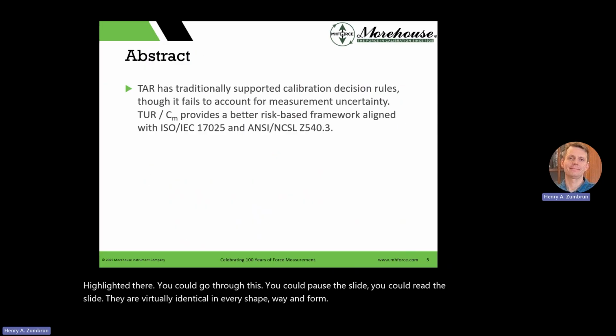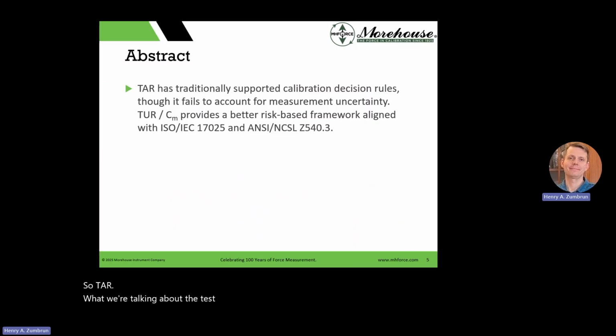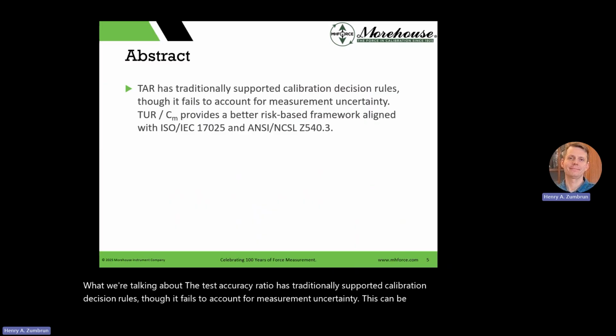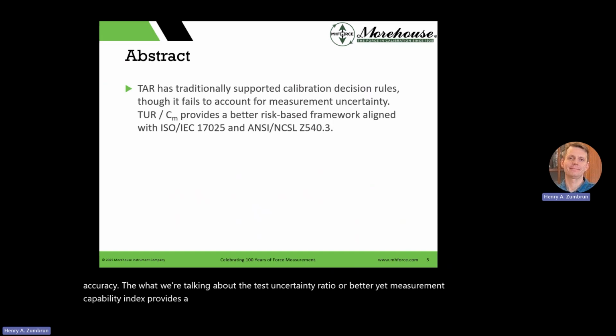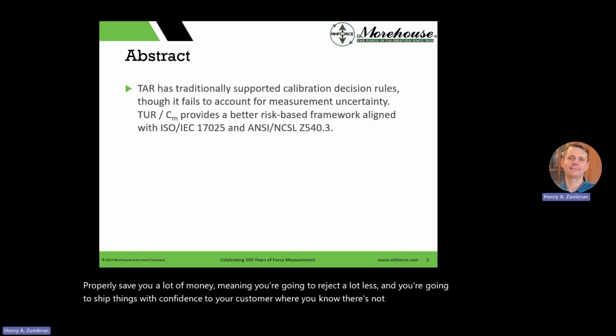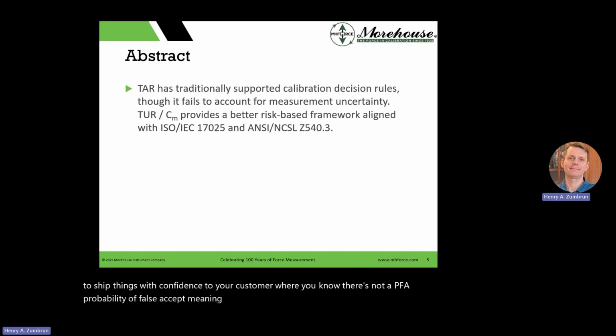So TAR, the test accuracy ratio, has traditionally supported calibration decision rules, though it fails to account for measurement uncertainty. This can be very problematic depending on how that manufacturer designed and quantified their accuracy. The test uncertainty ratio, or better yet, measurement capability index, provides a better risk-based framework. And if you're doing things properly, that is going to save you a lot of money, meaning you're going to reject a lot less and you're going to ship things to your customer with confidence, where you're pretty sure, better than 98% sure, that what you're sending them and the data you're sending them is correct. And when you say something passes, it actually passes.